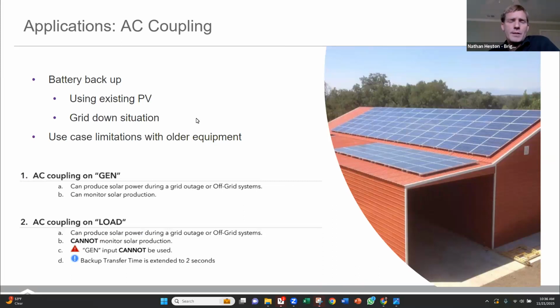How about AC coupling of systems? So with AC coupling, there are a lot of similar ways you would want to use AC coupled systems. If you've already got an existing PV array, you'll want to be able to have battery backup for that array, and you would use an AC coupled system in that instance. So what we're calling a retrofit. The array is already there, it's already AC coupled. We want to go in and add battery backup, but we don't want to have to pull a permit to change the array, for example, or change an interconnection agreement. Those are good examples of using AC coupling. That array is already there.